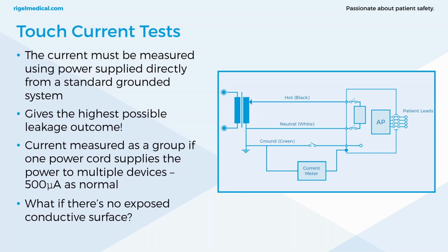Now, this is in NFPA 99, they actually recommend this. It must be undertaken with a suitable adapter, which is plugged into an outlet on the system. They need to ensure that the neutral conductor is used and not what would be the live or hot conductor. And then once the test has been done, you just remove it after the measurement's been completed. And obviously this is hazardous, but it needs to be carried out by someone that knows what they're doing.